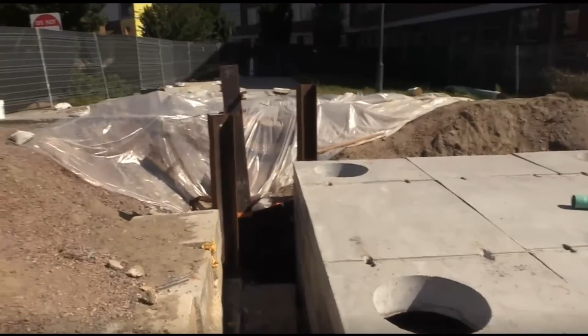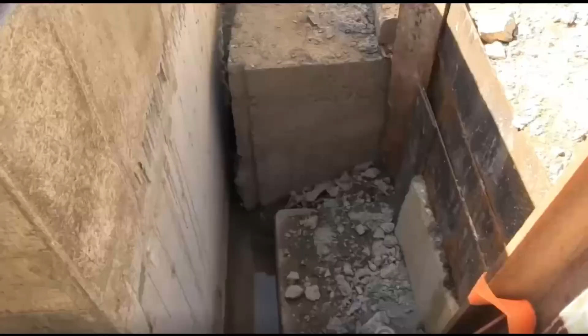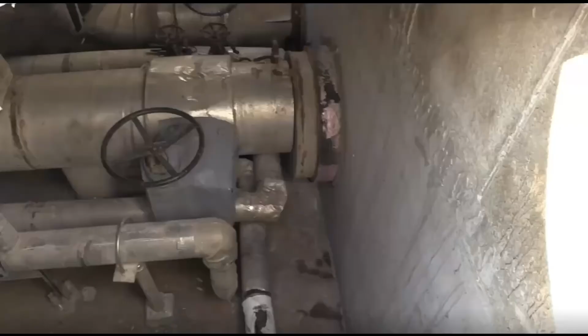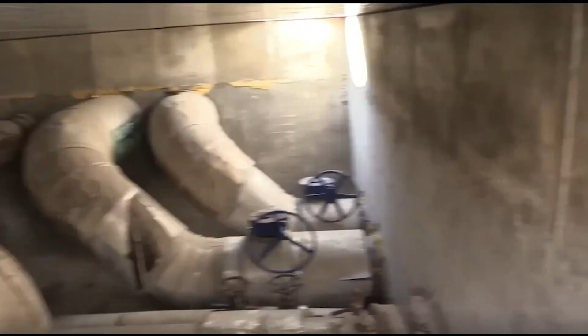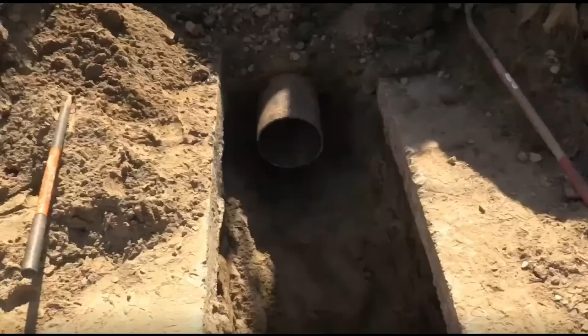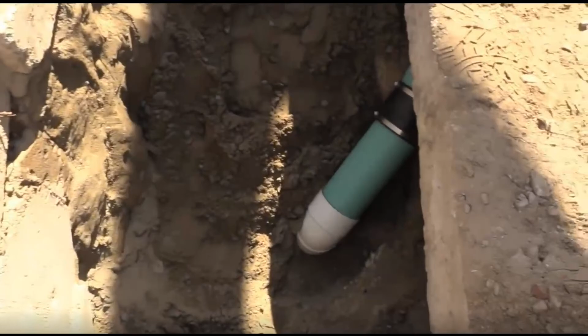This is one of 42 utility vaults on campus, and is really the hub between North and South Campus. So it's one of the most critical vaults on campus. Isolating the utilities prior to the project would be detrimental to the HVAC and heating systems, both on North and South Campus. And we really needed to keep this live while we were doing the construction. So access to valve work, maintaining thrust block anchors, and moving of equipment was critical to maintaining the system's operation.